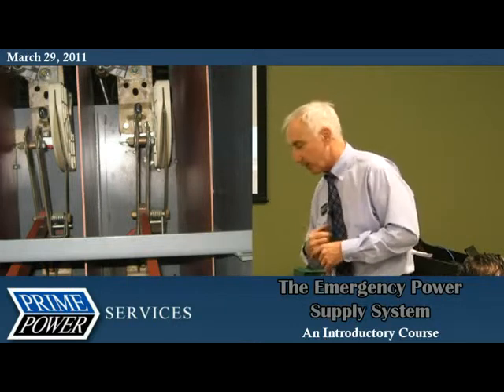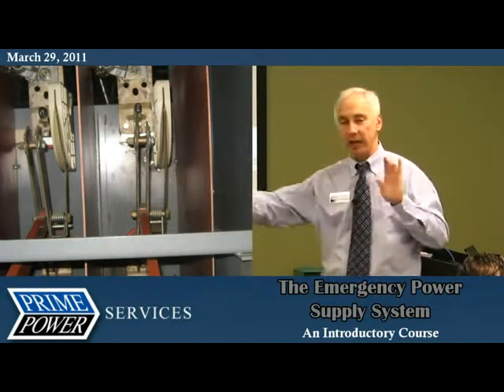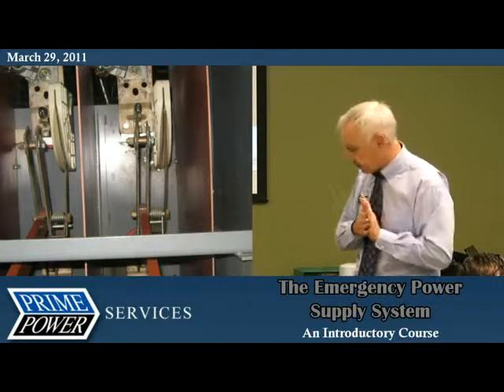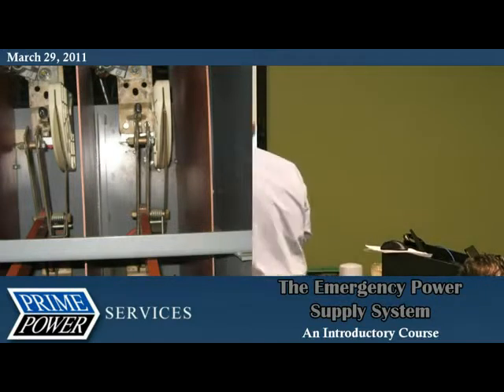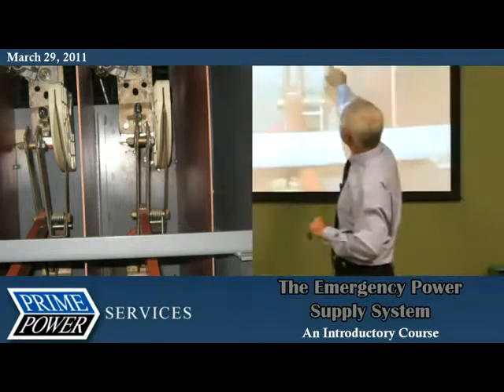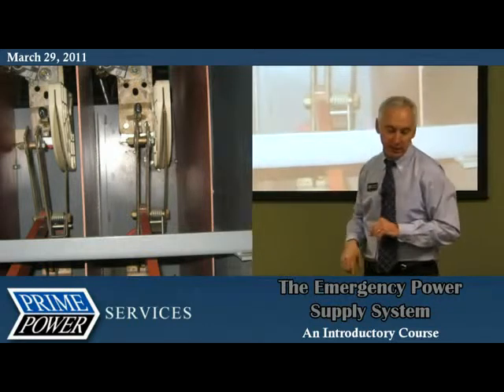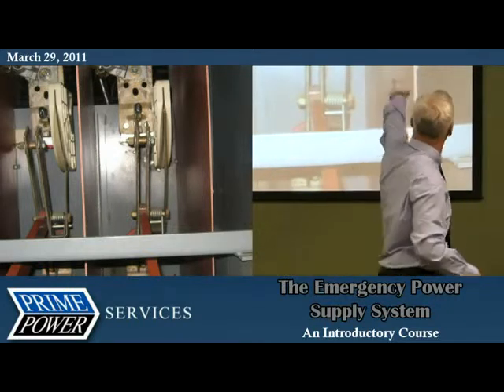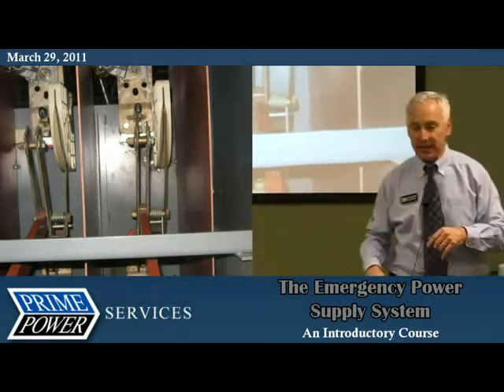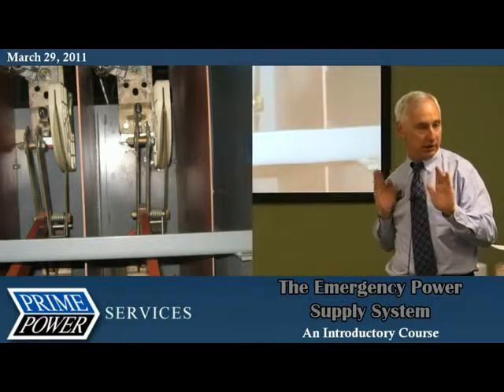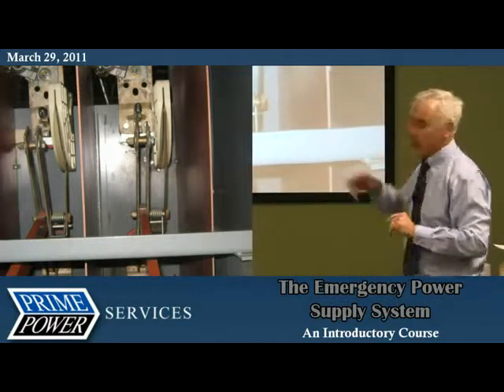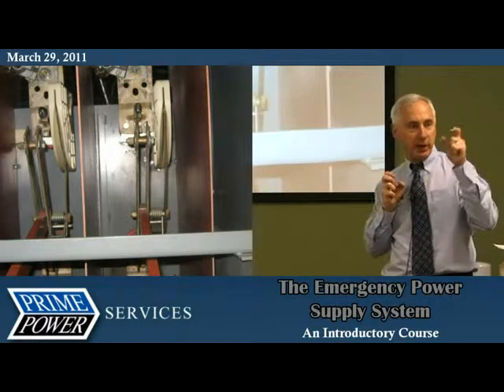This particular switch had never been serviced in over 20 years. The deal is, this is the main contacts. This is a sacrificial contact called an arcing contact. It comes out through that arc chute, so it's the last thing to open. The main contacts pull away so we don't burn them.